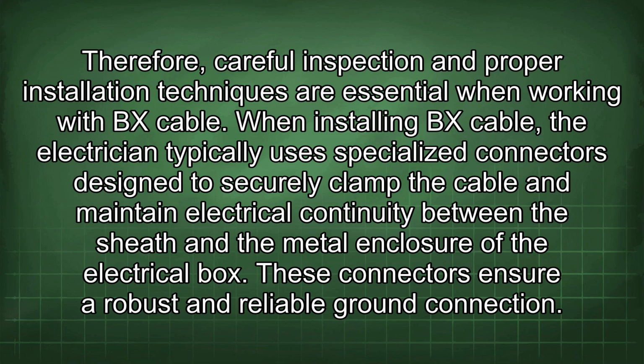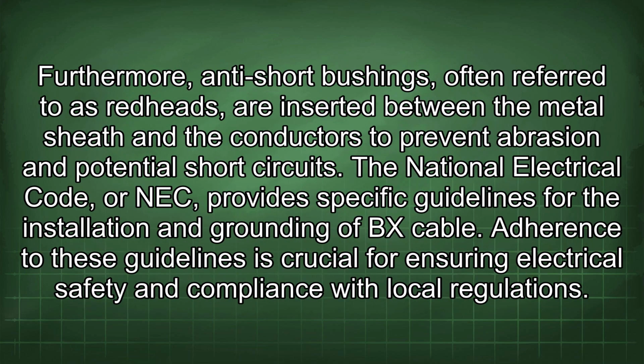When installing BX cable, the electrician typically uses specialized connectors designed to securely clamp the cable and maintain electrical continuity between the sheath and the metal enclosure of the electrical box. These connectors ensure a robust and reliable ground connection.